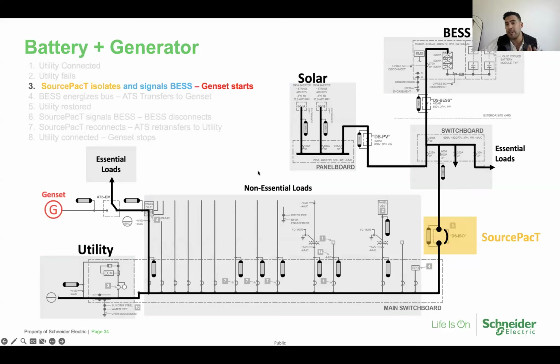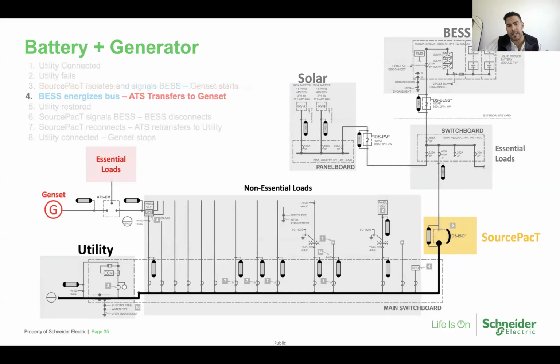At the same time, the ATS will send a start signal to the generator. Inverters and a battery energy storage system, just inverters in general, operate almost instantaneously. What I mean by that is when they lose power, they can change state from grid tie to a grid forming mode very quickly. They will come online much faster than a gen set. Once we detect that the generator is available, the ATS will transfer. The ATS operates as specified, and has been doing so for close to a century now. Transfer over to generator.